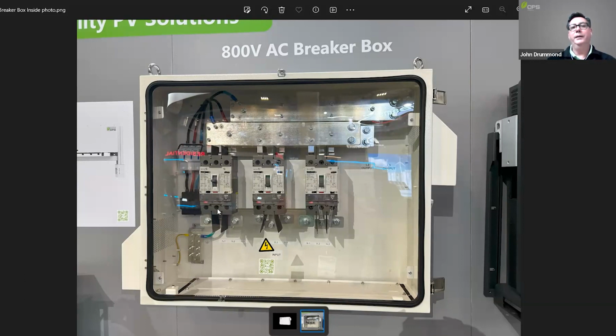It includes three 250 amp molded case circuit breakers. These have a 50,000 amp interrupt capacity, and this meets the requirement for having individual circuit protection for each inverter circuit.